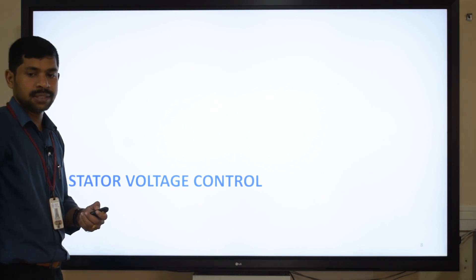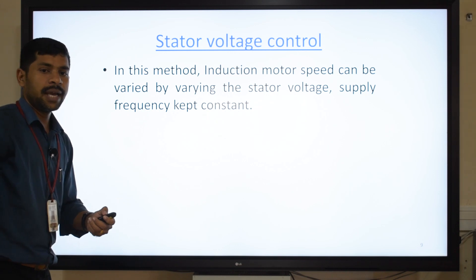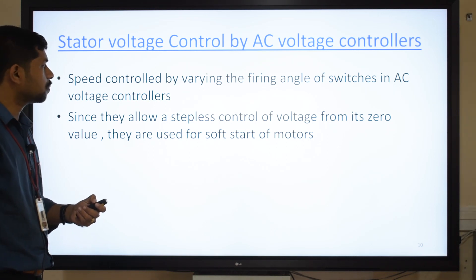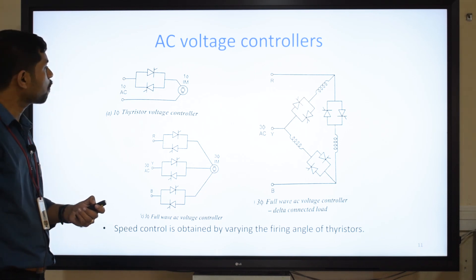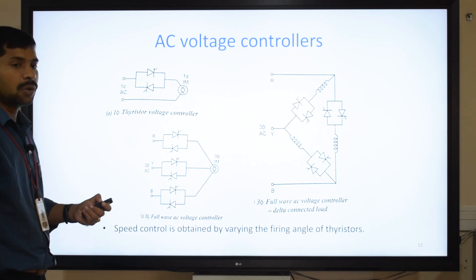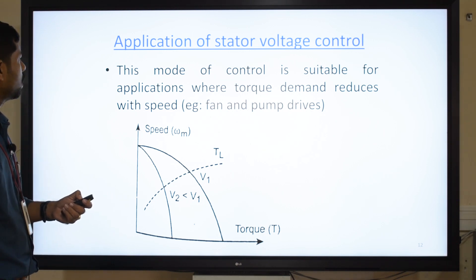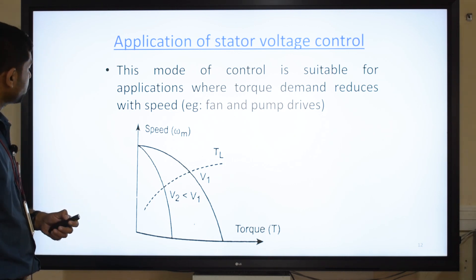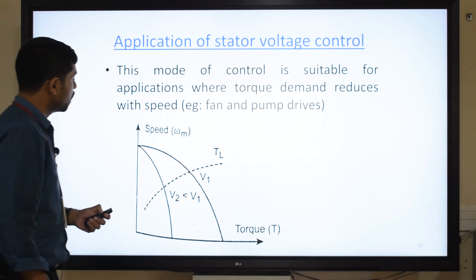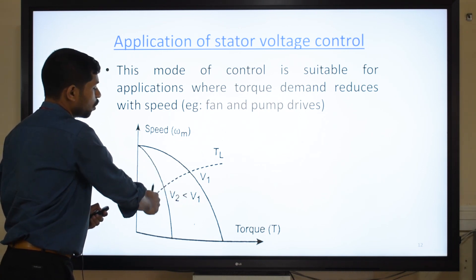Now let us see the first speed control technique: stator voltage control. In this method, supply frequency is kept constant and voltage is varied. This can be done easily using an AC voltage controller studied in power electronics. By varying the firing angle of the thyristors, we can control the RMS value of the output voltage and hence control the speed of the induction motor. This type of control applies where torque demand reduces with speed. As voltage V1 reduces, speed reduces, and accordingly torque is also reduced.